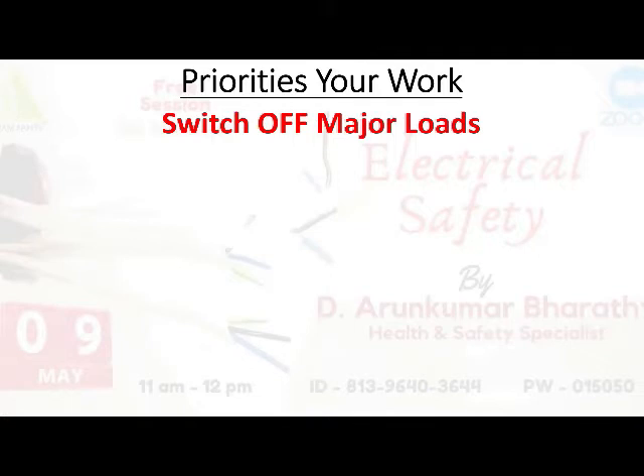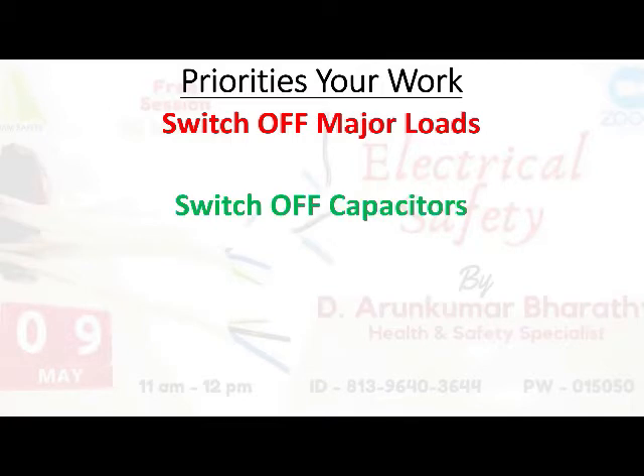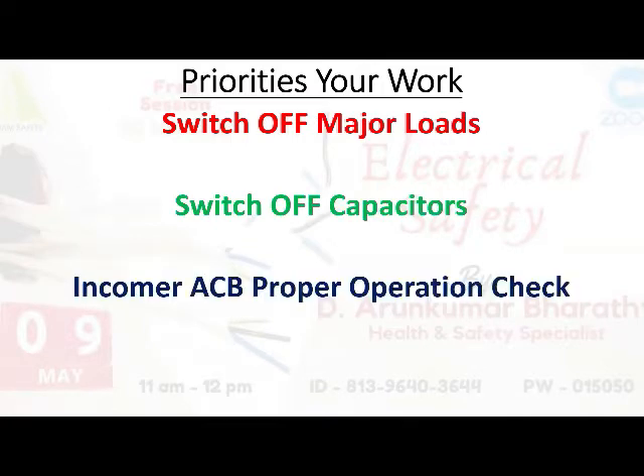Switch off the major loads first if they were on, and switch off all capacitors. Always check the incoming air circuit breaker for proper operation - meaning you don't need to switch it on, just check whether the mechanical operation is adequate and as per standard. Checking the incoming air circuit breaker is very important.